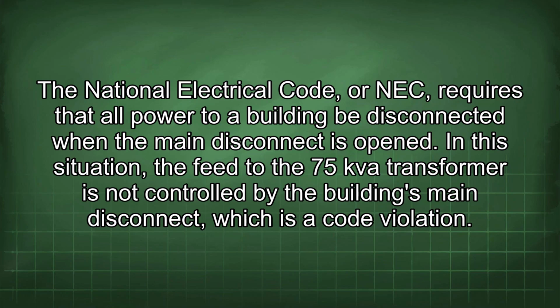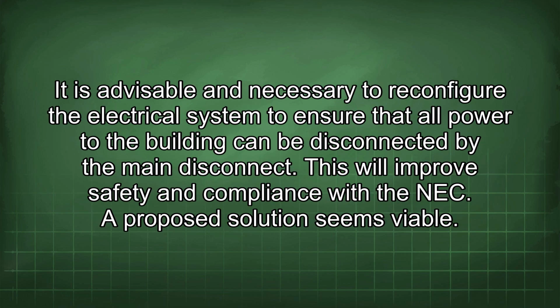The National Electrical Code, or NEC, requires that all power to a building be disconnected when the main disconnect is opened. In this situation, the feed to the 75 kVA transformer is not controlled by the building's main disconnect, which is a code violation. It is advisable and necessary to reconfigure the electrical system to ensure that all power to the building can be disconnected by the main disconnect. This will improve safety and compliance with the NEC. A proposed solution seems viable.